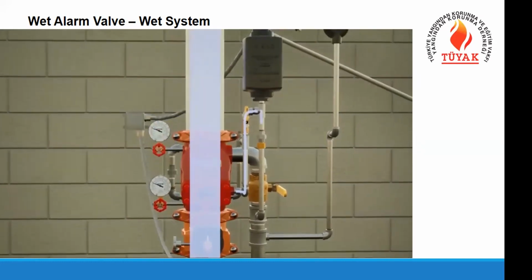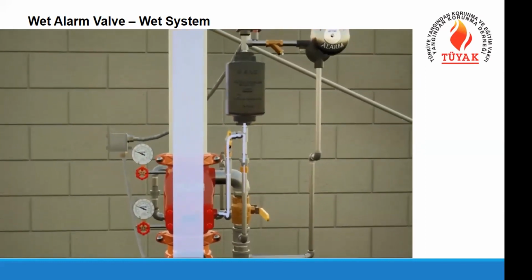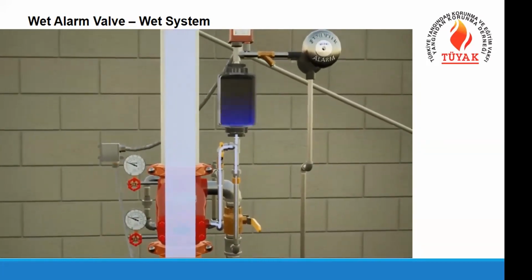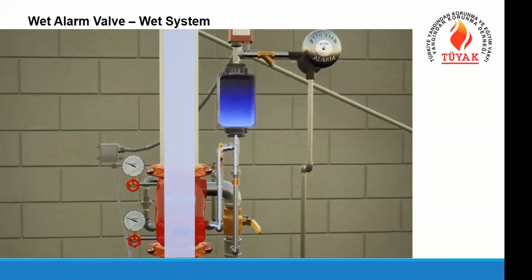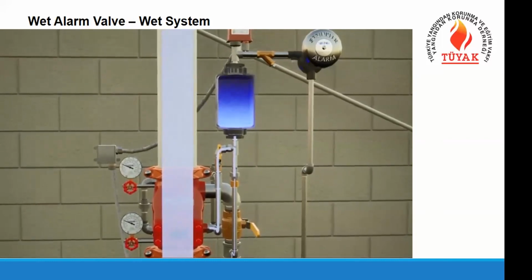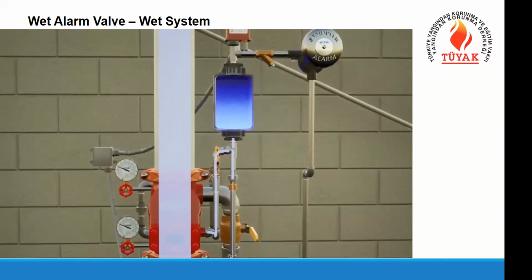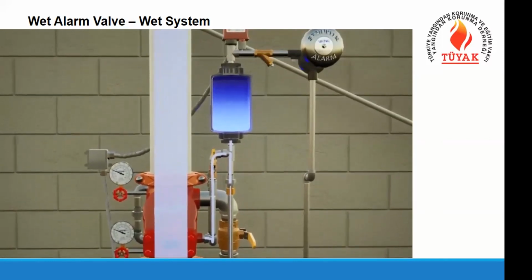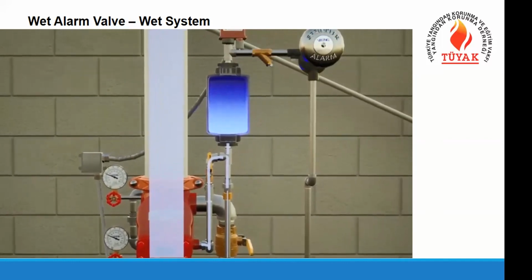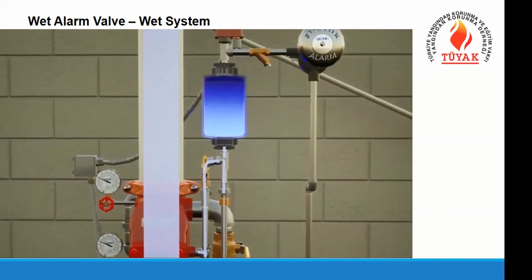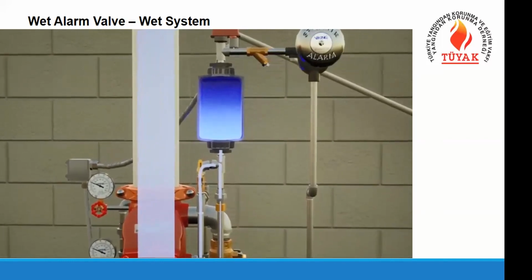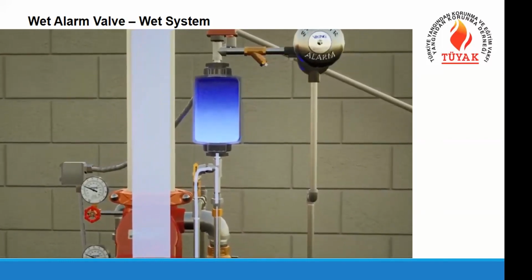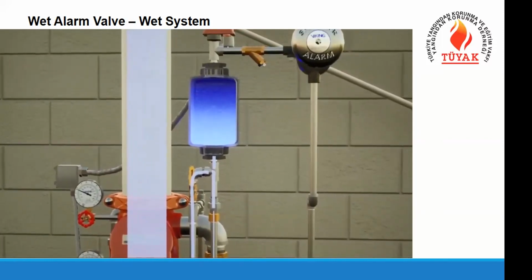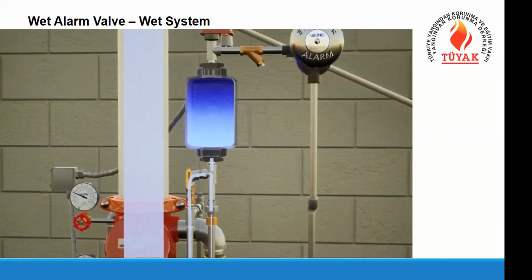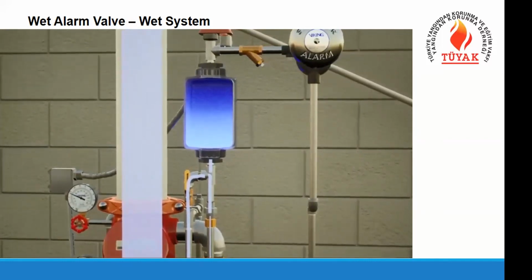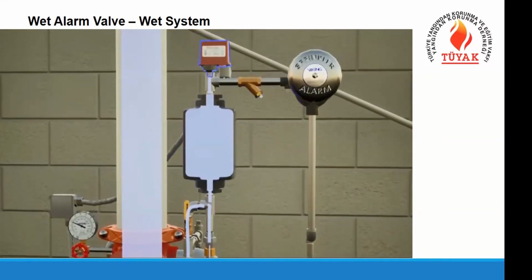If the system is equipped with a retard chamber, there will be a slight delay as the chamber fills before activating the water flow alarm. The retard chamber is a device that prevents false trips by containing up to a gallon of water flow prior to creating an alarm. Inadvertent water flow will only be able to fill a portion of the retard chamber's capacity. The alarm line is equipped with a 1/8 restricted orifice that allows the retard chamber to externally drain and reduces false alarms. During a fire, a consistent flow of water enters the alarm trim and fills the retard chamber faster than the restriction can drain, and the water flow continues through to the alarm devices.